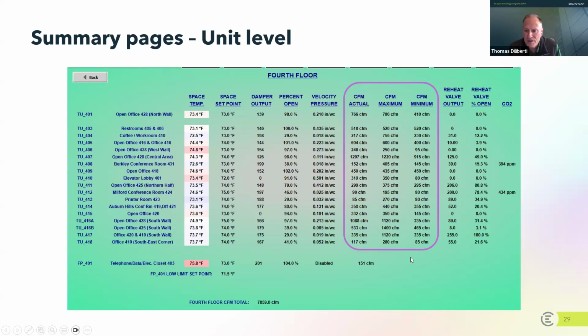And why I've brought this to your attention here is whenever you have VAV boxes, or what are called terminal units, that's what the TU stands for over here, these get programmed with a minimum and a maximum airflow. So this here, when you have restrooms with the same number, both as a minimum and a maximum, that's not normal. This was not designed to be the same. This is more typical, this coffee workroom where you have a maximum and a minimum flow that's different.